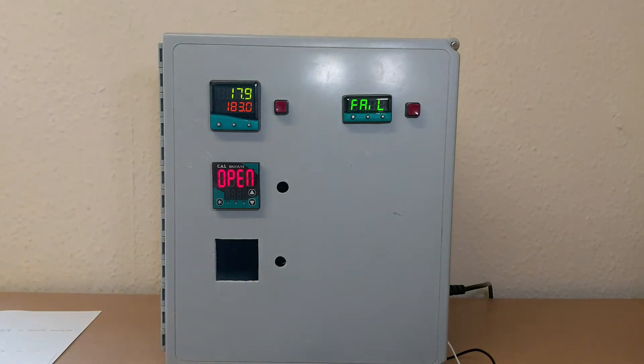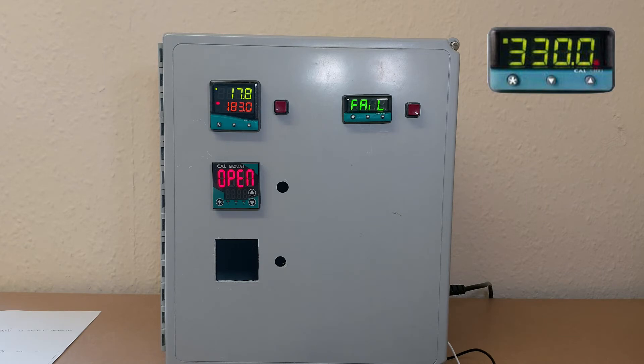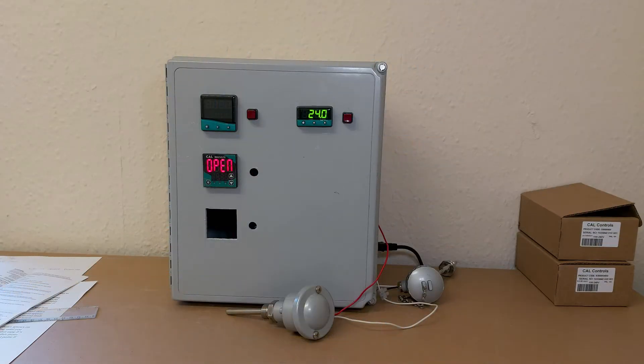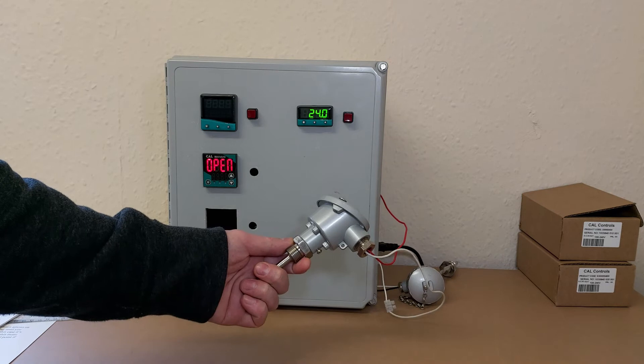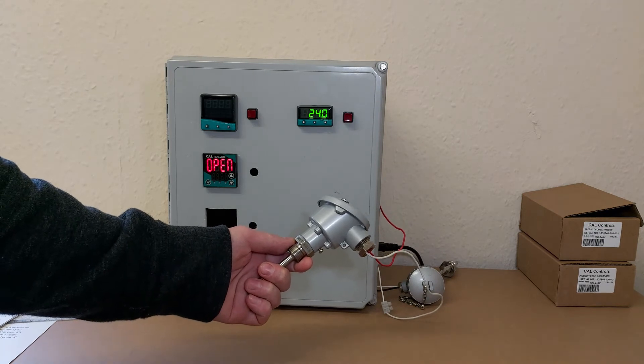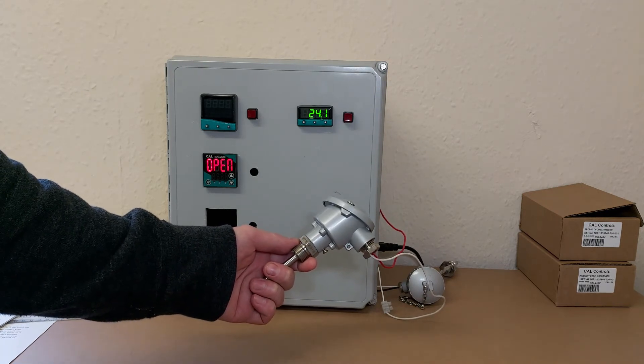Then I'll select RTD from the input menu in level 2. The term RTD is an abbreviation for resistance temperature detector. The most widely used type of RTD in industrial applications is the PT100. This is one of the most accurate types of temperature sensor.